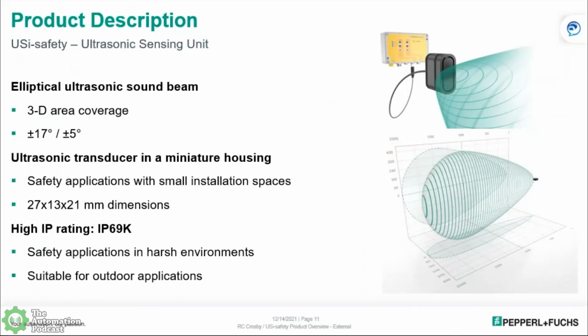Next, we'll dive into the transducers themselves a little bit. Again, as I noted earlier, the uniqueness of the elliptical sound beam gives you 3D area coverage at angles of plus or minus 17 and plus or minus 5 degrees. So at the widest point, around 1.5 meters away from the transducer face, you have a sound cone width of about 320 millimeters by 800 millimeters, as you can see on the little graph. But I'll blow up the graph in just a second.